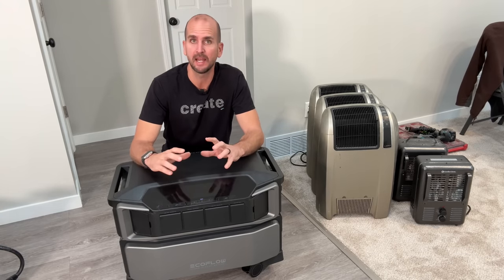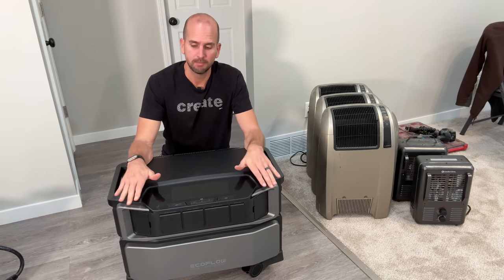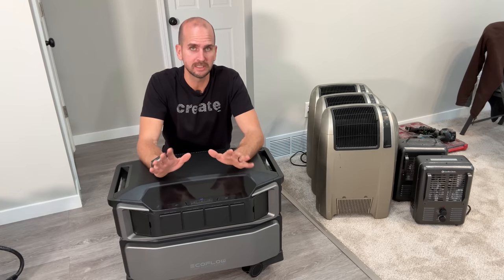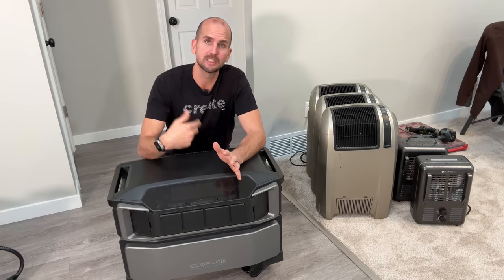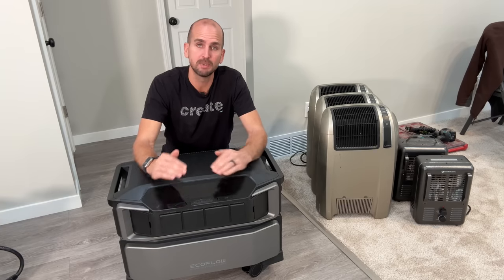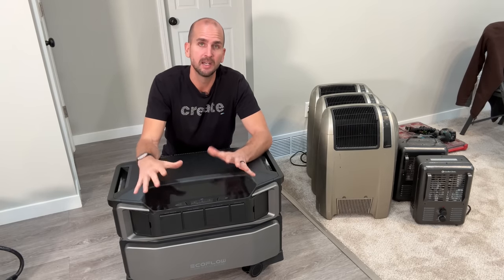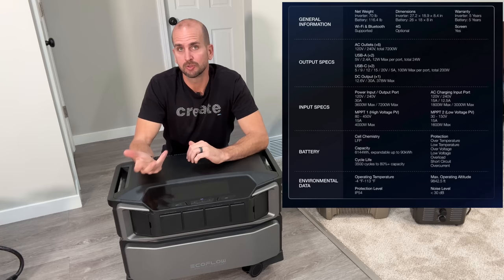This small 1000 square-foot home has a heat pump system — a Mr. Cool duct system — so it's all-electric with no gas for heat. I want to bring over four kilowatts of panels, add more capacity since six kilowatt-hours alone won't cut it, install the Smart Panel 2, and try to run the house off it. The batteries are lithium iron phosphate, rated for about 3500 cycles while maintaining 80% capacity — roughly 10 years of daily cycling. The warranty on the inverter and battery is five years.